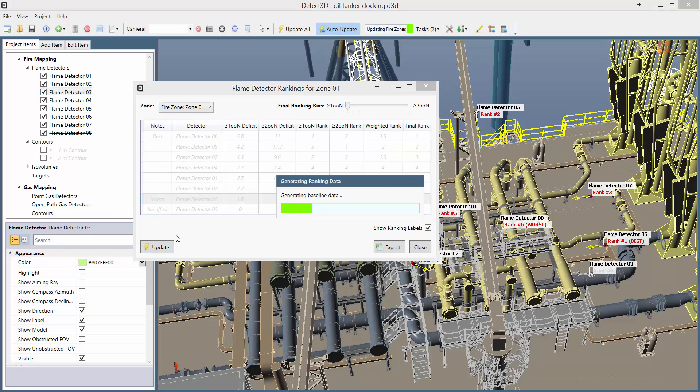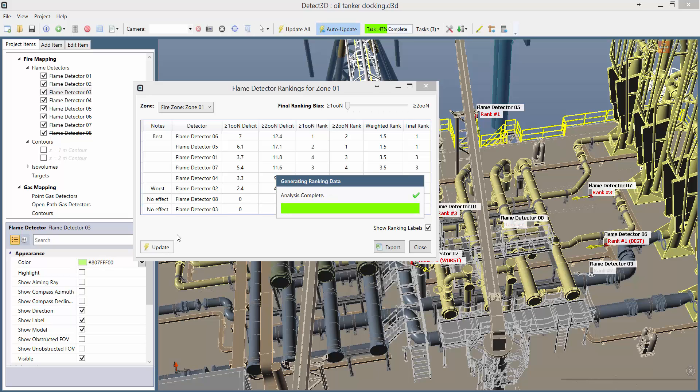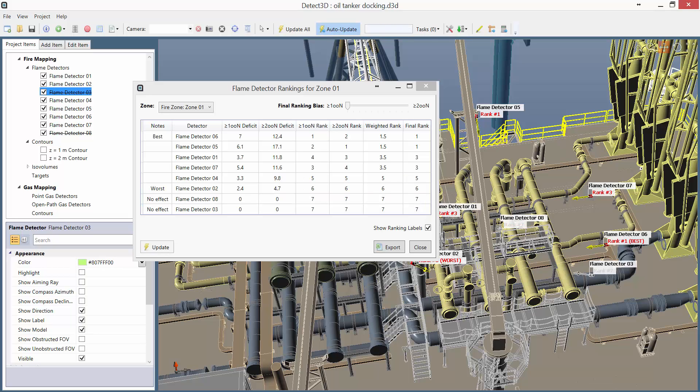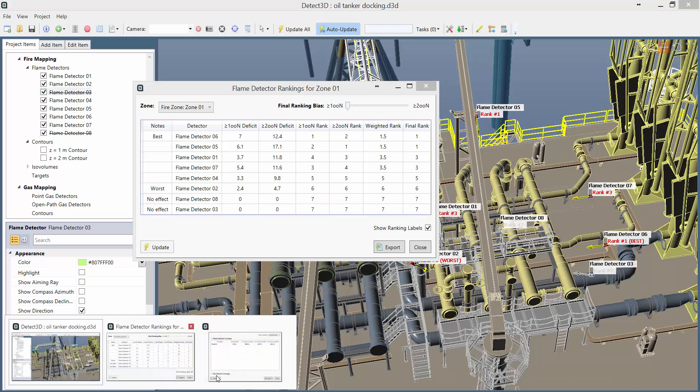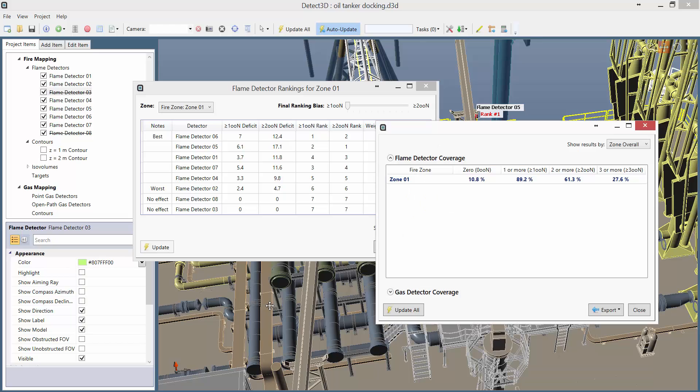Once the simulation has finished updating itself, and the ranking has also updated, we can now look at the new coverage results with Flame Detector 8 switched off, and as expected we have 89.2% 1 out of n coverage, below our target of 90% but not too far off.